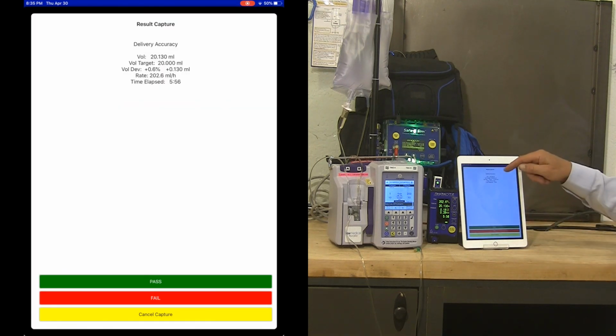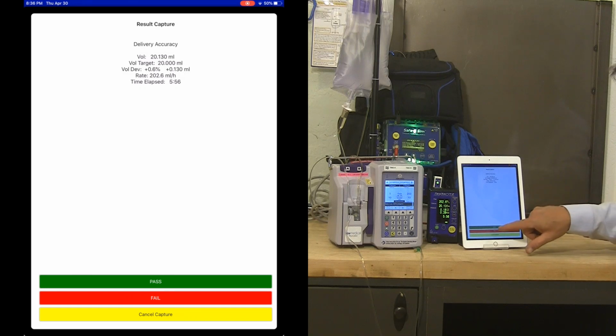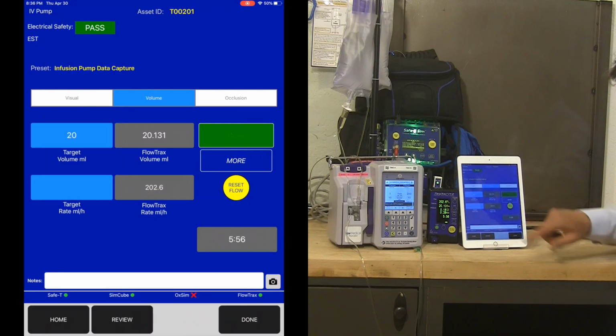I hit capture. I've got delivery accuracy volume 20.130, volume target of 20, deviation plus 0.6%. You don't get much better than that. With a delta of 0.13 and a rate average of 202, time elapsed 5 minutes 56 seconds. Clearly that's a passing result, so I'm going to hit the big green pass button on the screen.